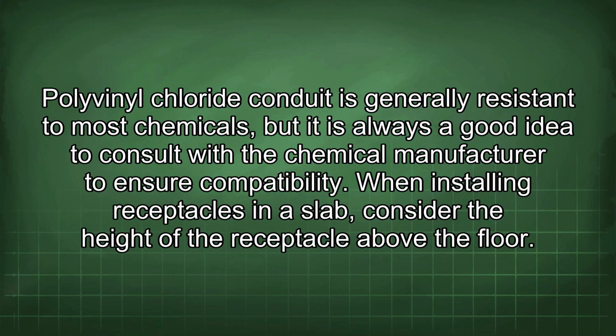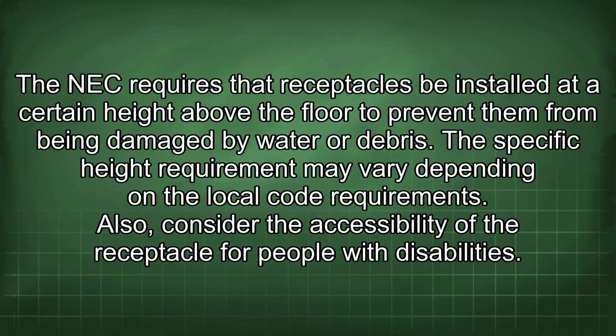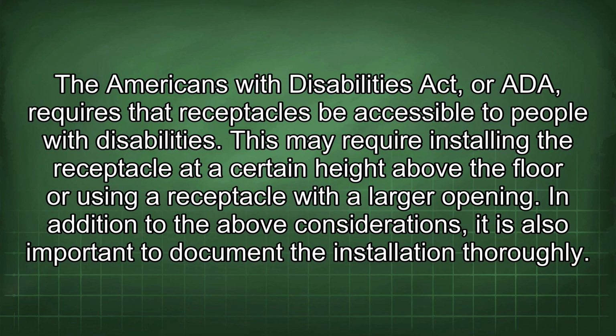When installing receptacles in a slab, consider the height of the receptacle above the floor. The NEC requires that receptacles be installed at a certain height above the floor to prevent them from being damaged by water or debris. The specific height requirement may vary depending on the local code requirements. Also, consider the accessibility of the receptacle for people with disabilities. The Americans with Disabilities Act, or ADA, requires that receptacles be accessible to people with disabilities. This may require installing the receptacle at a certain height above the floor or using a receptacle with a larger opening.